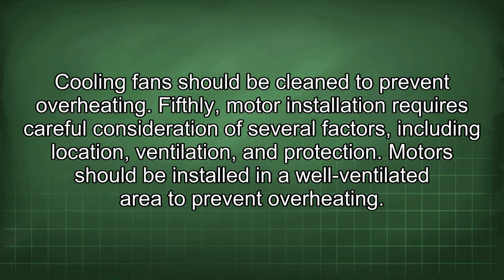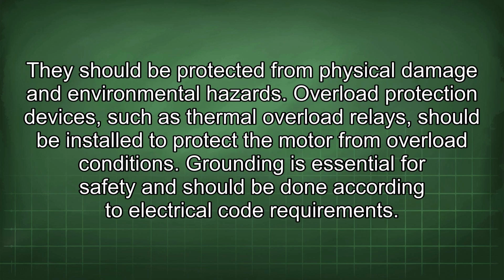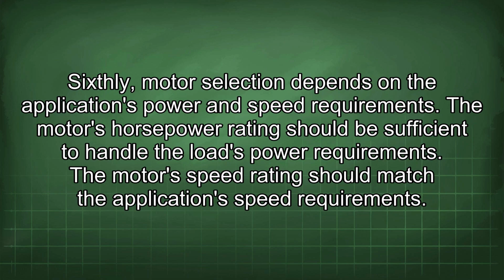Motors should be installed in a well-ventilated area to prevent overheating. They should be protected from physical damage and environmental hazards. Overload protection devices, such as thermal overload relays, should be installed to protect the motor from overload conditions. Grounding is essential for safety and should be done according to electrical code requirements. Sixthly, motor selection depends on the application's power and speed requirements.